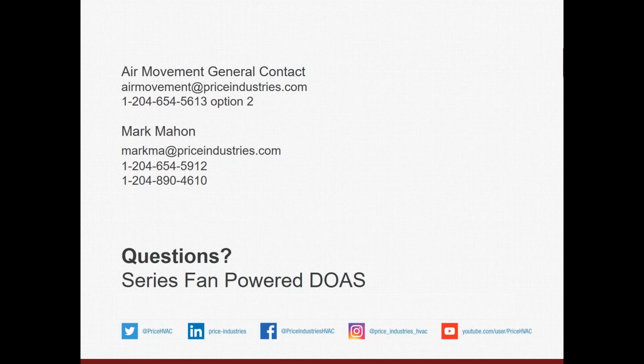Mark, I'll add on to that. So Brian Wolford with ACI, VP of Engineering. To answer a little bit more of Linda's question: heating and cooling, yes, water flows. When it's in deadband, water shuts off to that coil, heating and cooling. The next part that meets Washington State Energy Code is we actually will back that fan down to under the threshold of 0.12 watts per CFM, which Mark has kindly given us some charts on what that threshold is. So that's how that meets the Washington State Energy Code. Heating, cooling, chilled water in deadband, that water shuts off, fan pulls back to under 0.12 watts per CFM.